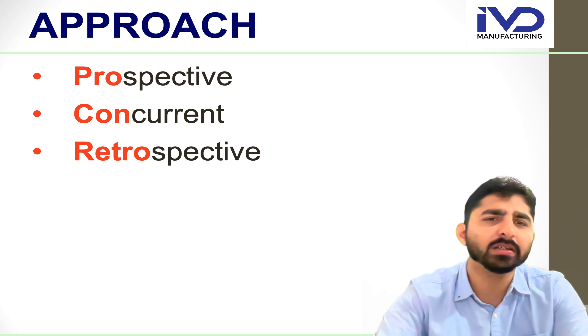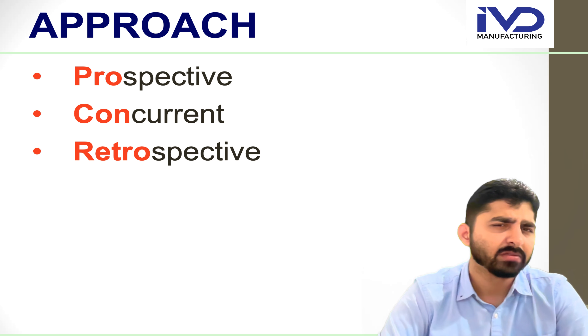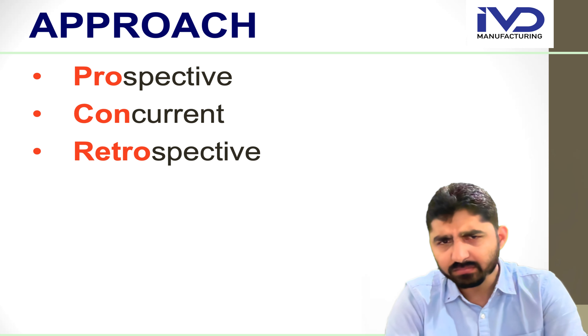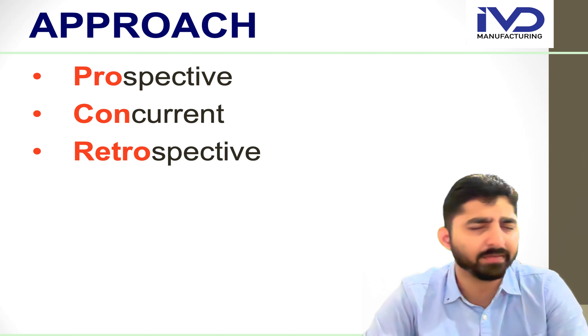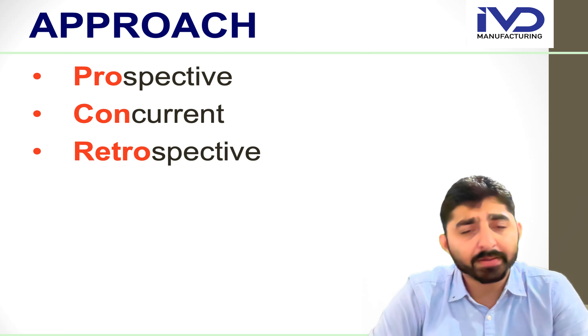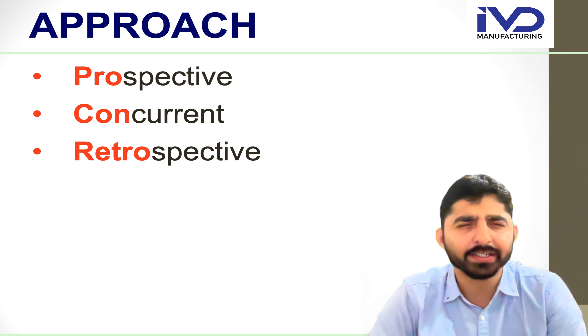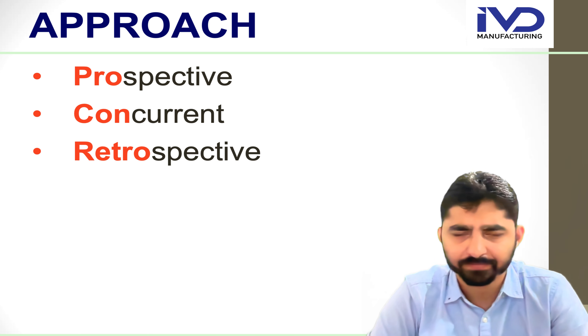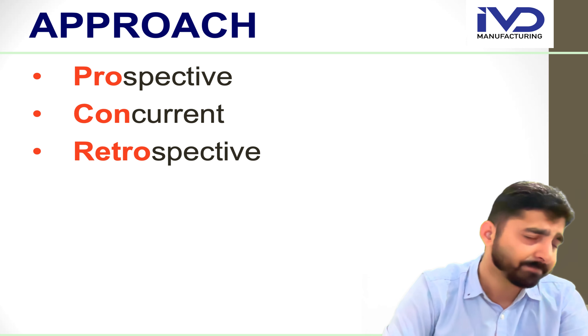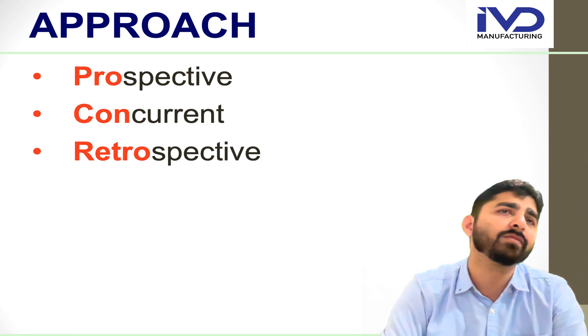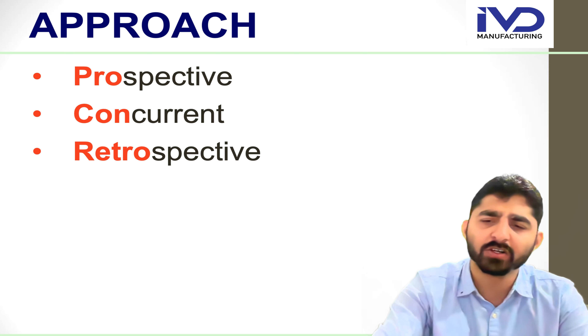There are mainly three types of PV approaches. The first is prospective, the second is concurrent, and the third is retrospective. If you are building a new facility from day one, that is prospective PV. If during implementation you need to make changes, that is the concurrent PV approach. And if you have already set up the premises and processes but have not yet started PV, and then conduct it using already available data, that is called retrospective PV.